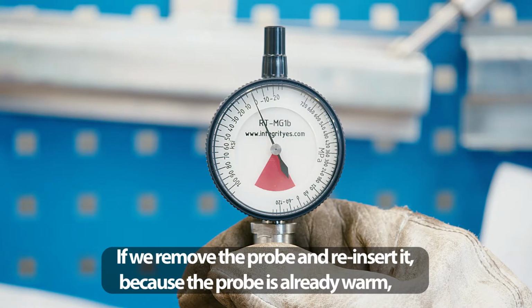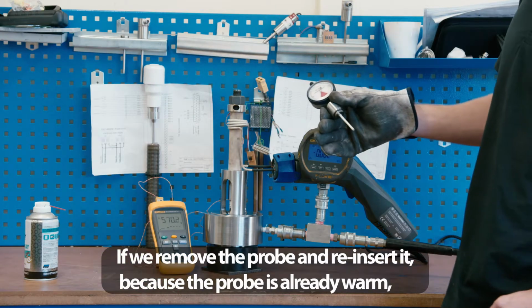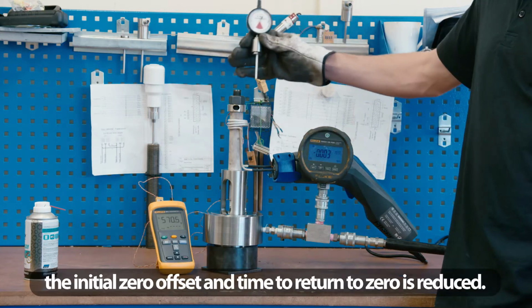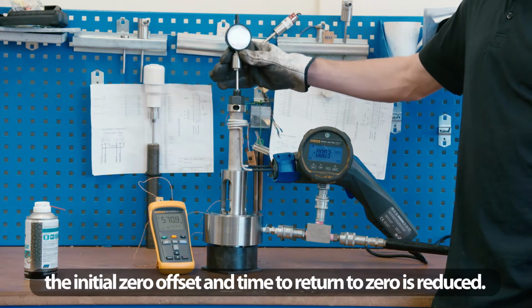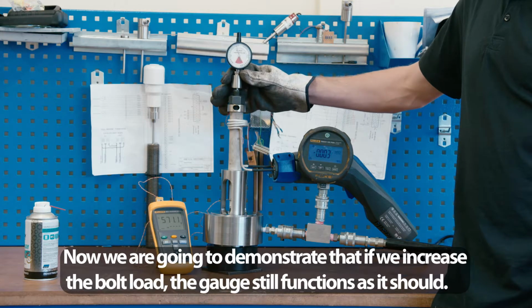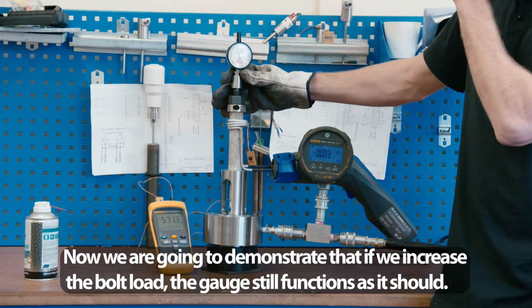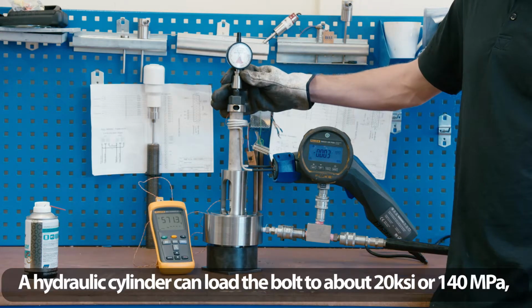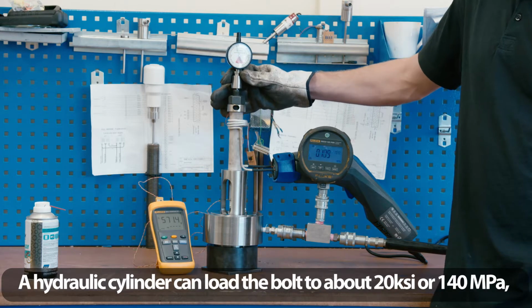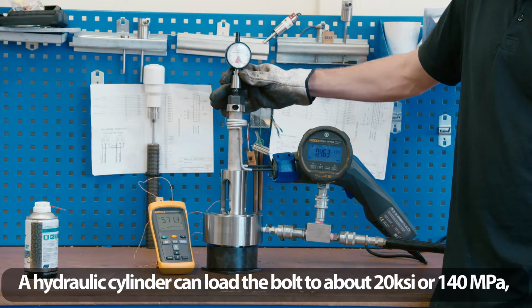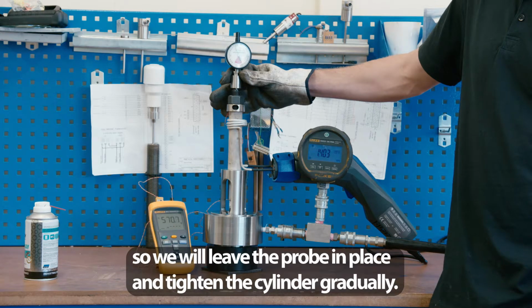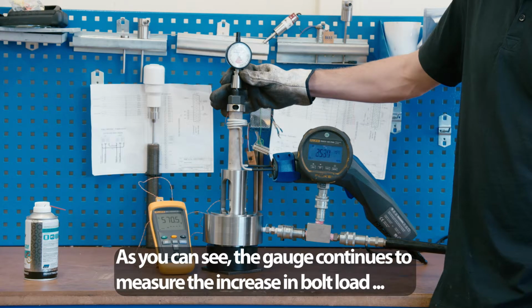If we remove the probe and reinsert it, because the probe is already warm, the initial 0 offset and time to return to 0 is reduced. So now we are going to demonstrate that if we increase the bolt load, the gauge still functions as it should. A hydraulic cylinder can load the bolt to about 20 ksi or 140 MPa, so we will leave the probe in place and tighten the cylinder gradually.